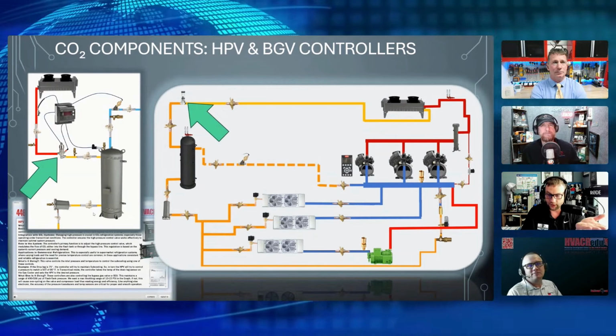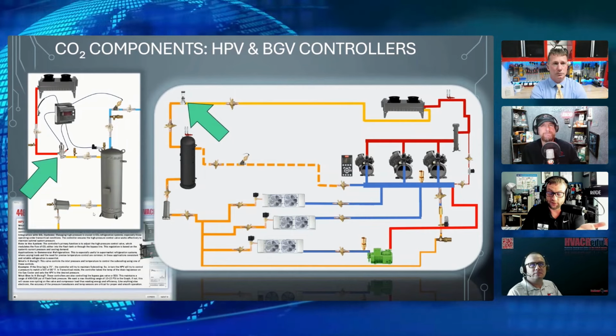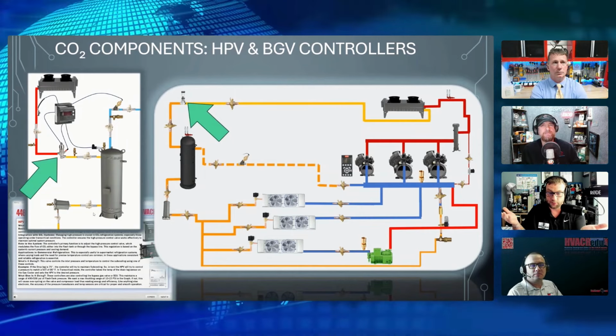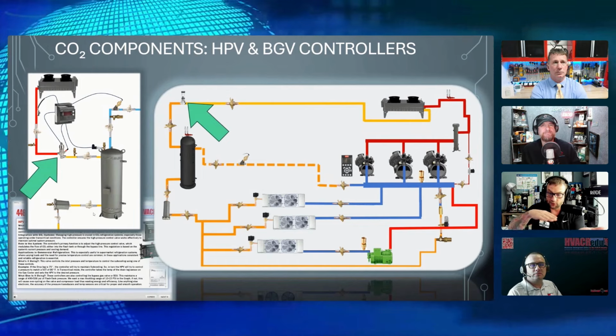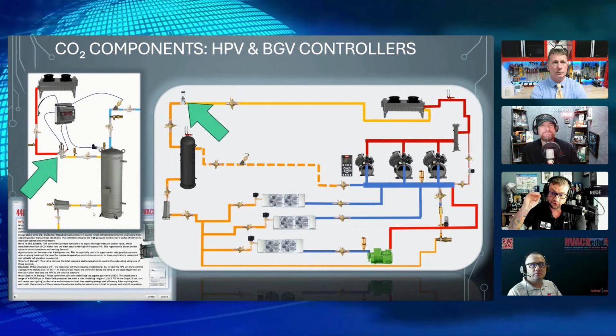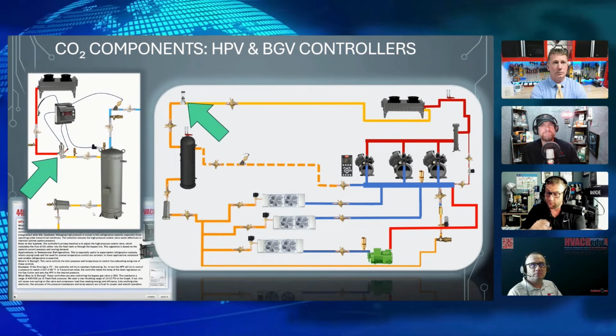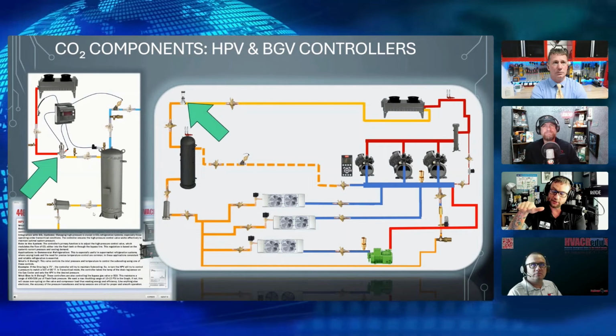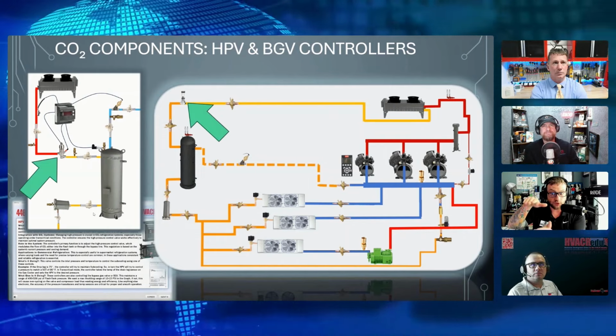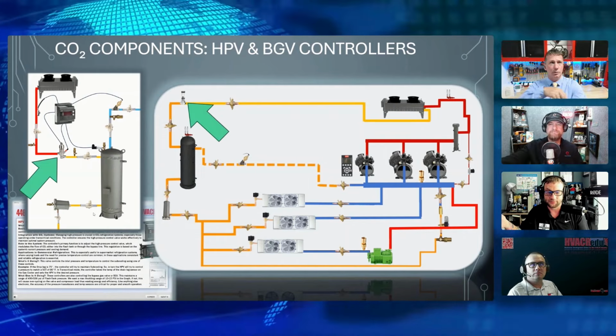So we have the actual drop leg temperature sensor. Let's just say it's at 75. So theoretically, with math and a PT chart, doesn't take a scientist, we go 5 degrees above that as far as our saturated pressure. So that HPV is mitigating and trying to regulate a pressure of 80 degrees saturated, which gives you 5 degrees of subcooling. 5 degrees subcooling. Yep. Correct.